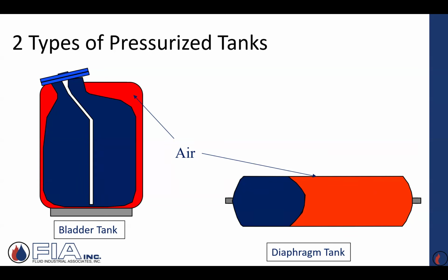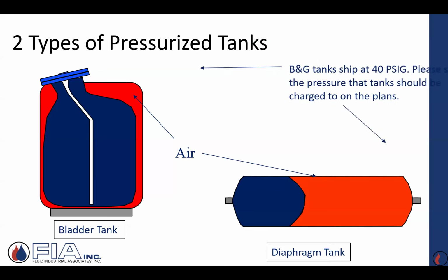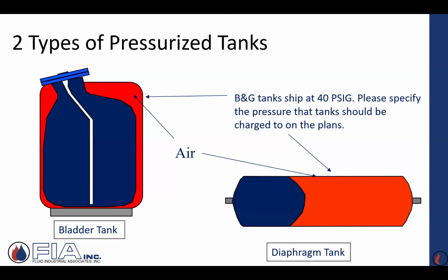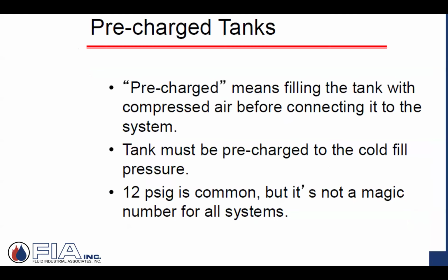And then at some point, as you get into software and you're doing your software selection, which we'll go through an exercise later on in a couple of weeks, at some point, the diaphragm tank doesn't make sense, and I'm going to this bladder style. And it's designed for those bigger systems with more water, more expansion. They come pre-charged. Again, we'll spend more time on this, but the pre-charge of a diaphragm or a bladder has to match the fill pressure requirements of the system you're attaching it to. We'll get into more details, but it's a very important piece of information.